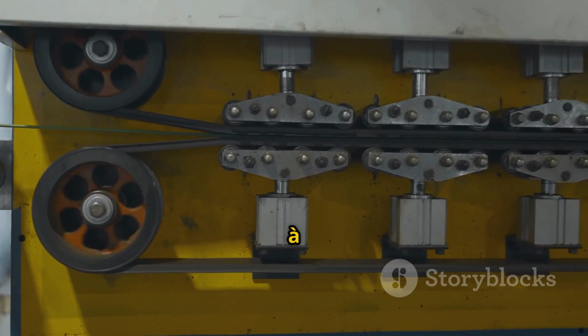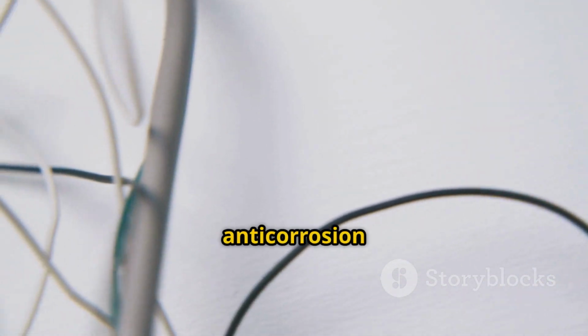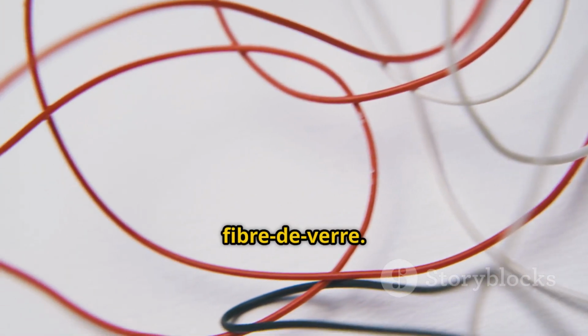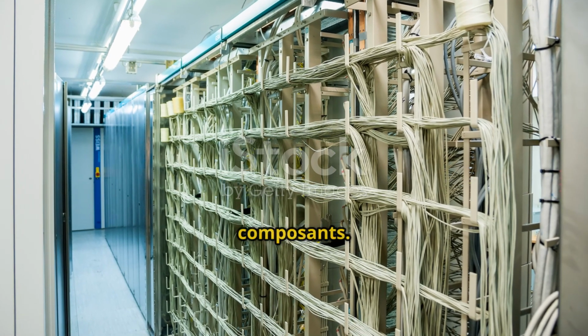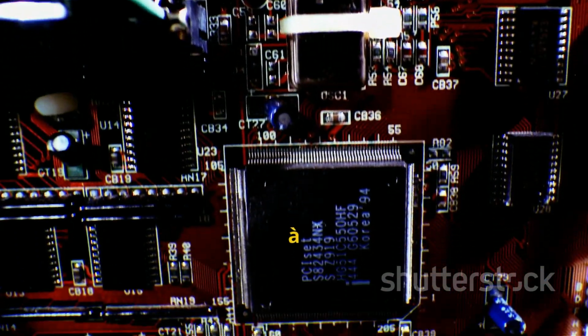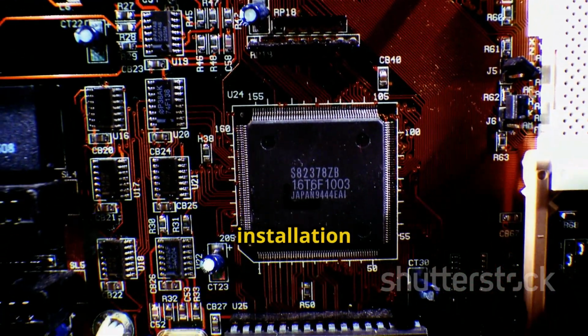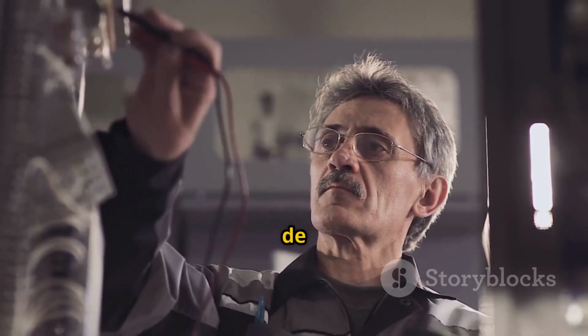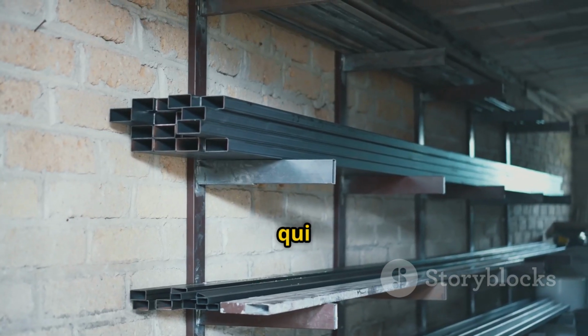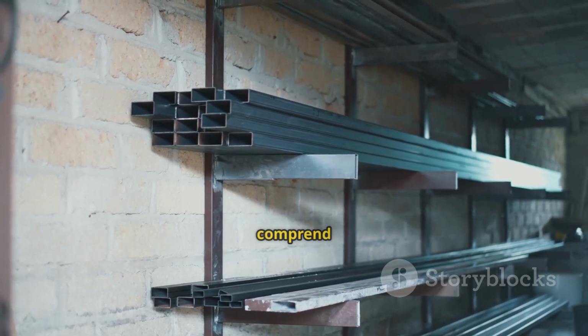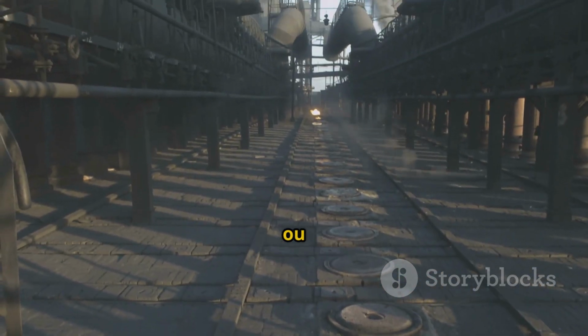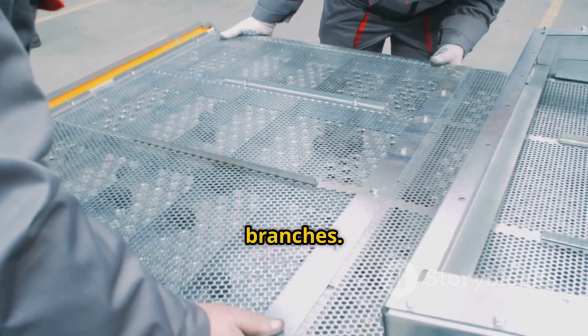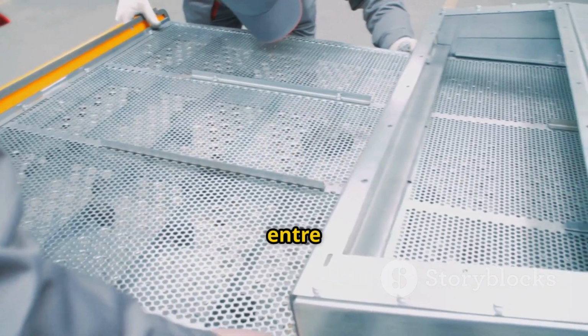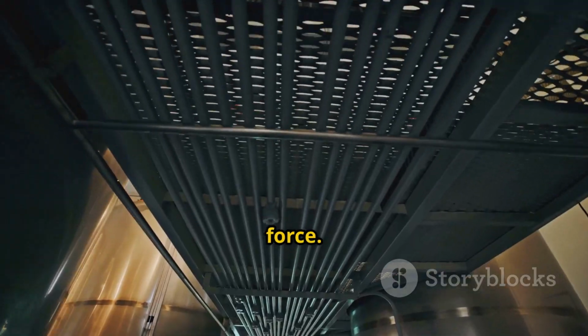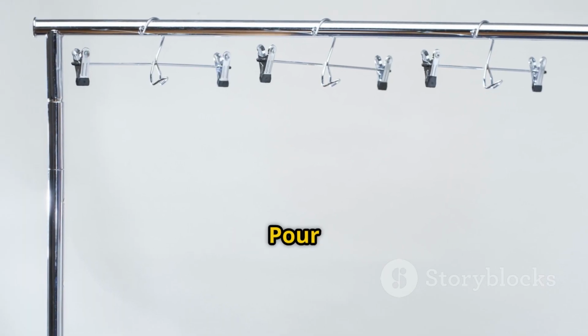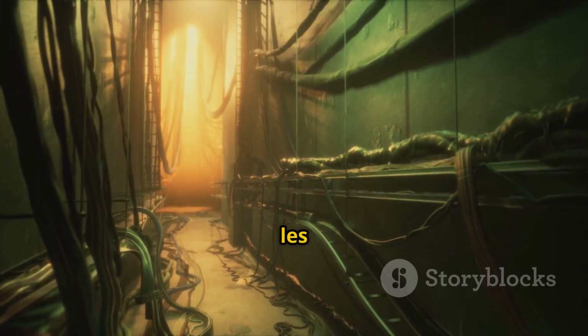They're not just simple troughs. They're engineered components, designed to handle specific loads, span distances, and withstand harsh environmental conditions. Forming the skeletal framework of an electrical installation, a cable tray system is a collection of components that fit together. It includes straight sections that form the main pathways. It also includes fittings to change direction or level: elbows for turning corners, T's for creating branches, risers for vertical transitions between floors. This modularity is a major strength. It lets engineers design custom pathways for buildings and industrial facilities, navigating around obstacles like pipes, support beams, and other equipment. The system is supported by hangers or brackets attached to walls, ceilings, or floors.